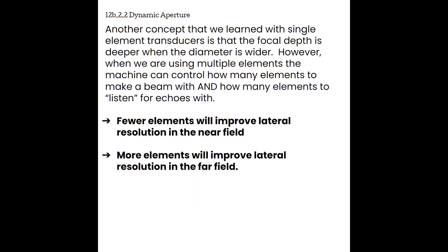Another concept from single element transducers is that focal depth is deeper when the diameter is wider. With multiple elements, the machine can control how many elements to use for transmitting and listening — this is a dynamic aperture, meaning a changeable hole for creating the beam and receiving echoes. Fewer elements improve lateral resolution in the near field for shallow imaging; more elements improve lateral resolution in the far field. The machine looks at the maximum depth being used and adjusts the number of active elements to optimize lateral resolution accordingly.